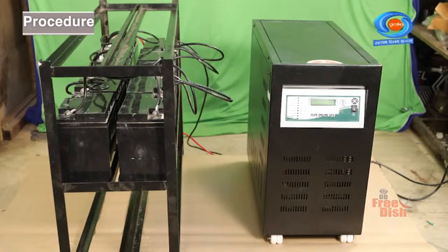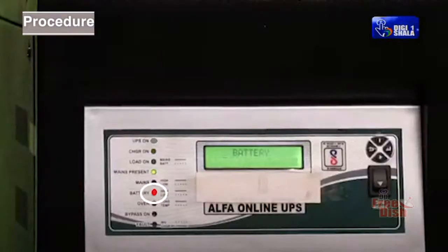Recharge the battery immediately for at least 4 hours. Check and test the UPS with the recharged battery and rectify the fault by referring to the troubleshooting sequence block diagram. If the replace battery red LED is still on, replace the battery.